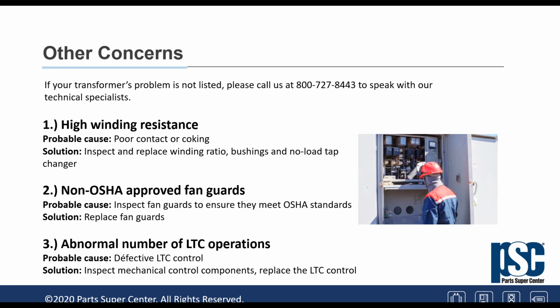And again, OSHA said that the concentric rings of the fan guard have to be no more than half an inch apart. Also, the guard has to be at least 6 feet from the ground. That's what OSHA says. And again, you don't have to change the fan, but on our G transformers, we can replace the fan guard.